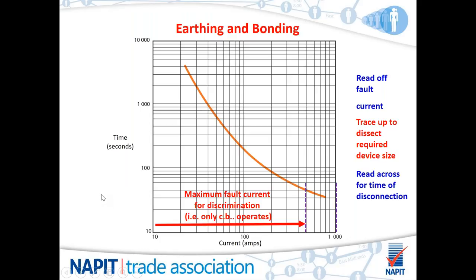Current that has been calculated or measured can be read across the bottom. And then when you get to the point where that current is, you go up to the fuse in question, whatever size that fuse is, and once it intersects the curve, you can then read off the actual disconnection time for that protective device.